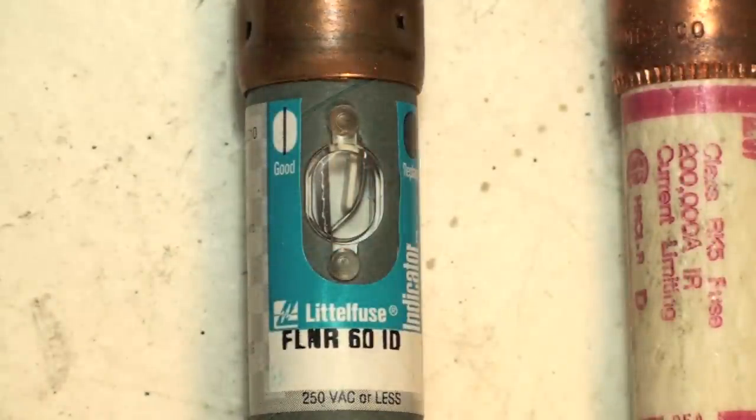There we go. Now you can see through that little window. This is an FLNR 60 ID, which means it's a time delay fuse, or dual element fuse, and it has a little window.